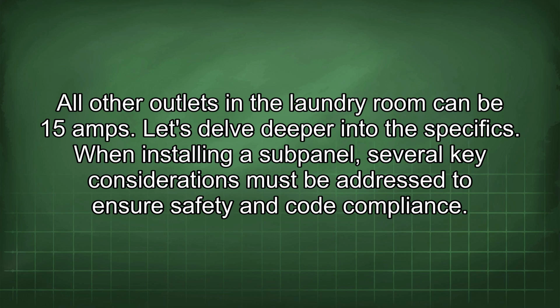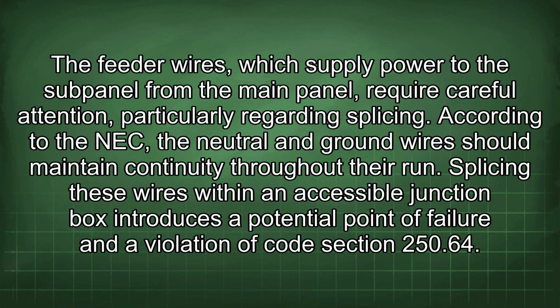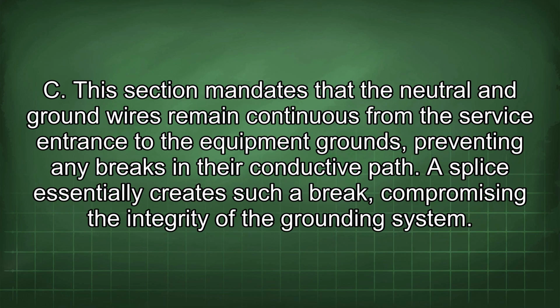When installing a subpanel, several key considerations must be addressed to ensure safety and code compliance. The feeder wires, which supply power to the subpanel from the main panel, require careful attention, particularly regarding splicing. According to the NEC, the neutral and ground wires should maintain continuity throughout their run. Splicing these wires within an accessible junction box introduces a potential point of failure and a violation of Code Section 250.64(C). This section mandates that the neutral and ground wires remain continuous from the service entrance to the equipment grounds, preventing any breaks in their conductive path. A splice essentially creates such a break, compromising the integrity of the grounding system.